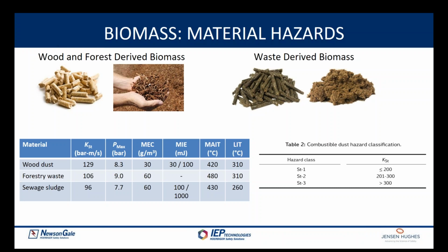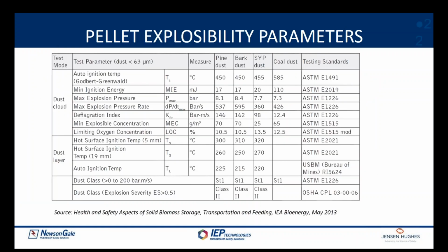These, again, should not be used for designing explosion protection or suppression systems or to characterize ignition sensitivity, because I'd like to emphasize that these parameters are not fundamental properties. This is taken from a publication on the transportation and feeding of bioenergy. It shows values for various explosion severity and ignition sensitivity parameters for pine dust and bark dust, and compares them to coal dust. As you can see, perhaps surprisingly, biomass dust can be as or more hazardous in terms of explosion violence and ignition sensitivity compared to coal dust.